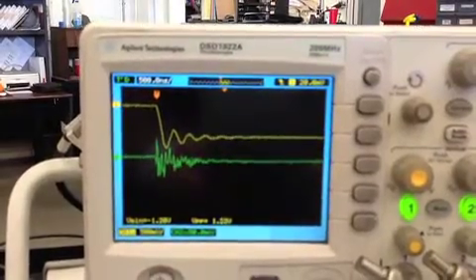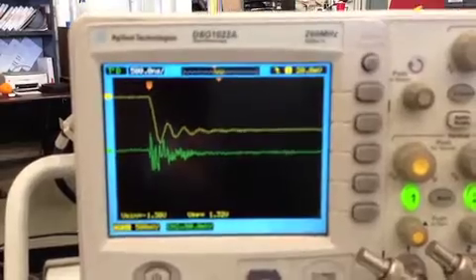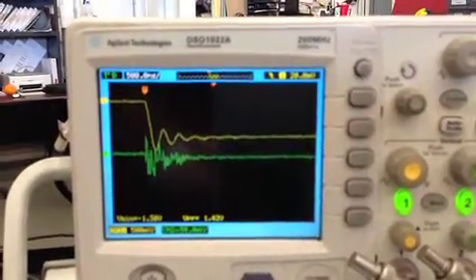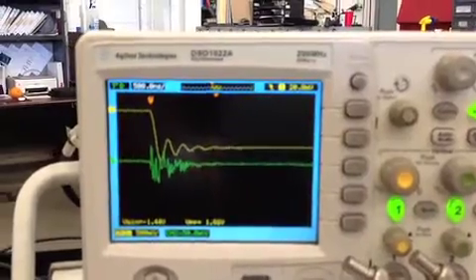Keep your eyes on the green line, the lower line, and we'll make a note when we reach the partial discharge. There we go, we're starting to see the activity.